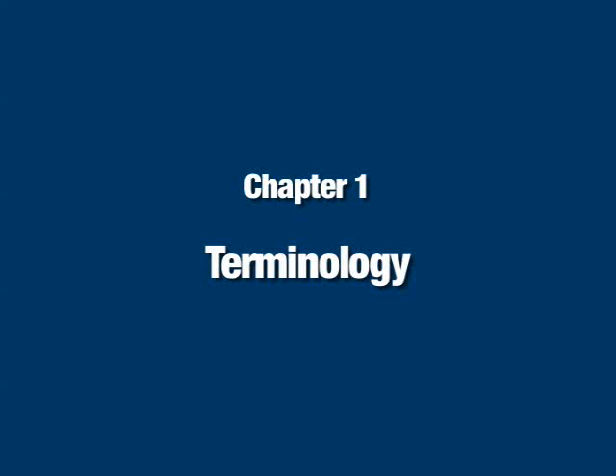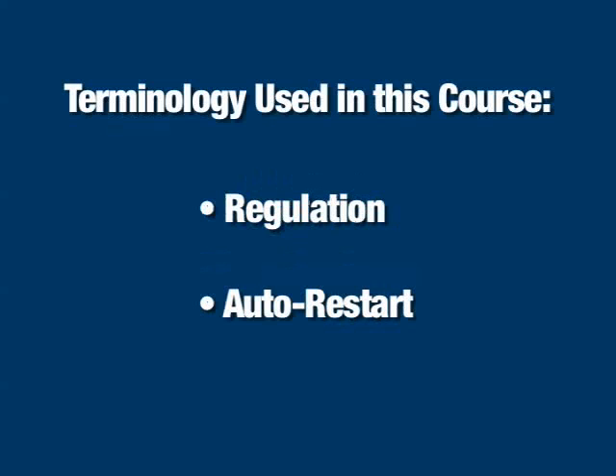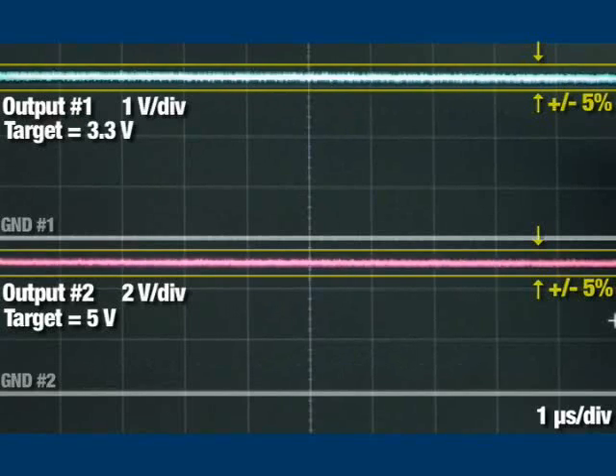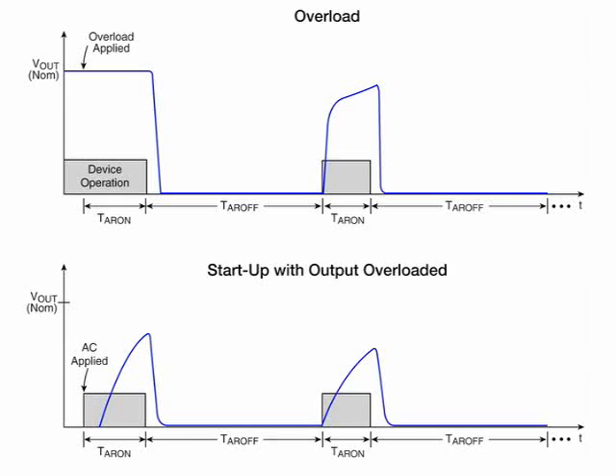Chapter 1: Terminology. We'll begin by defining 2 terms which will be referred to often during this course. The first term is regulation. When a power supply is in regulation, the controller is receiving feedback and all output voltages are stable, constant, and within specified tolerance limits.